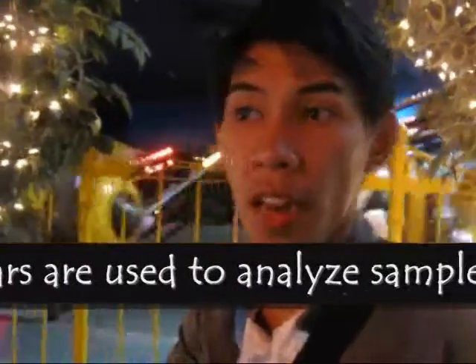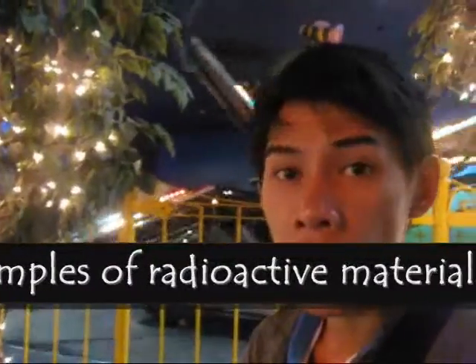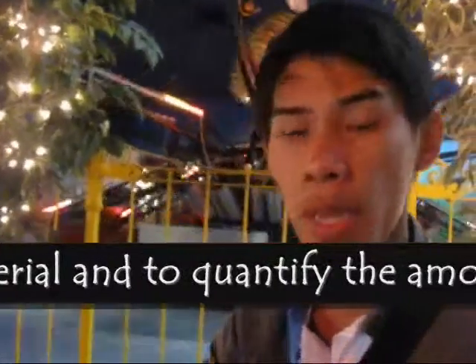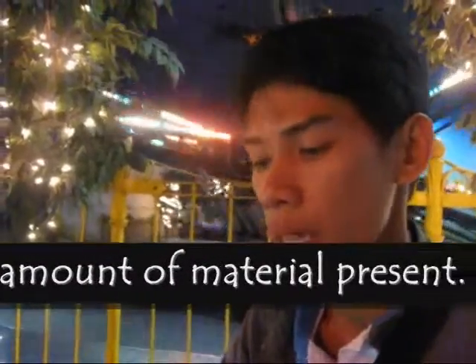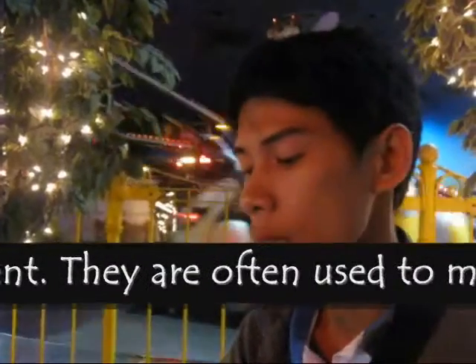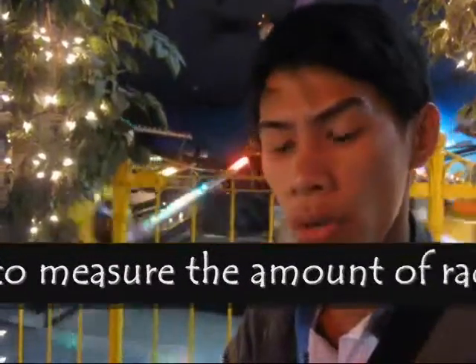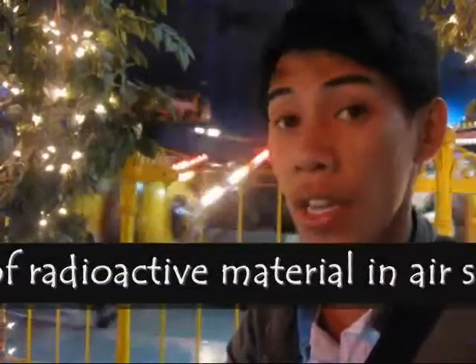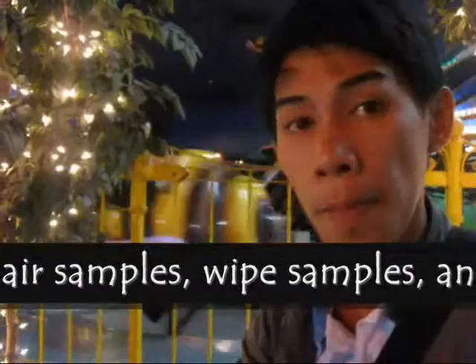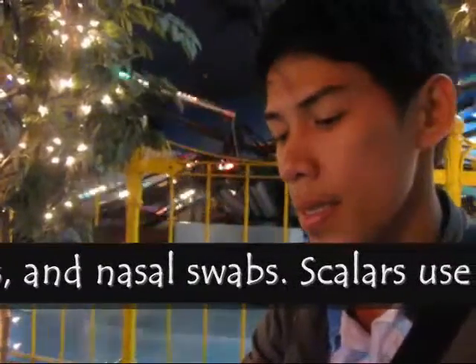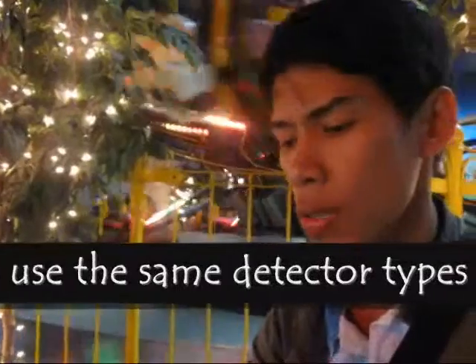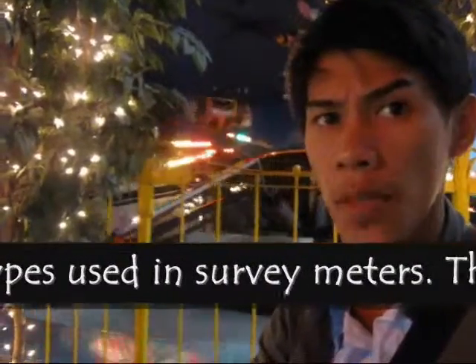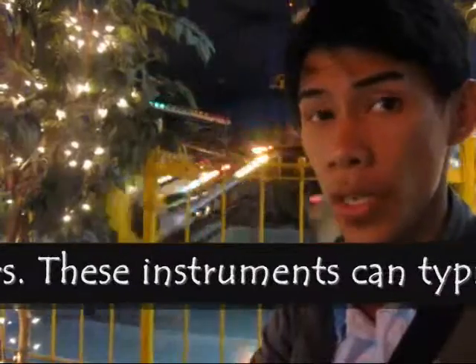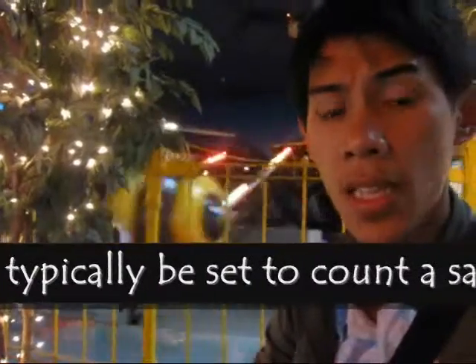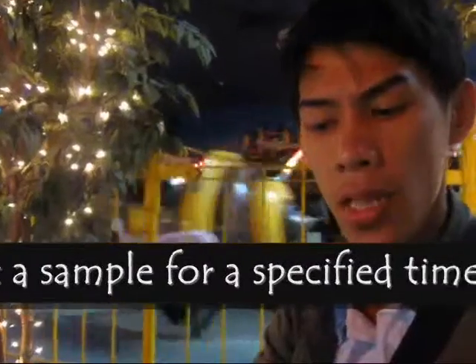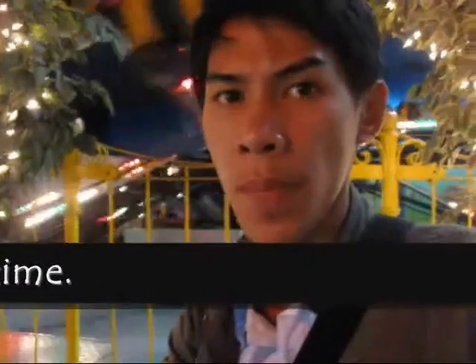Number 2, scalers. Scalers are used to analyze samples of radioactive materials and to quantify the amount of materials present. They are often used to measure the amount of radioactive materials in air samples, wipe samples, and nasal swabs. The scalers use the same detector types used in survey meters. These instruments can typically be set to count samples for a specified time.